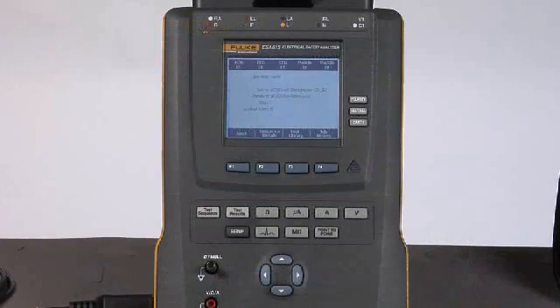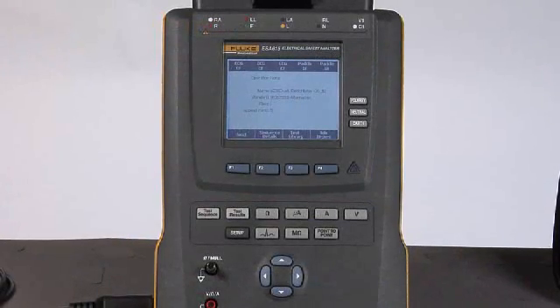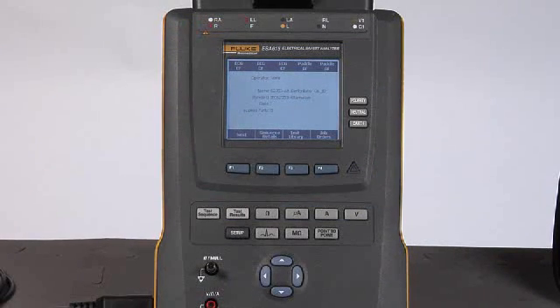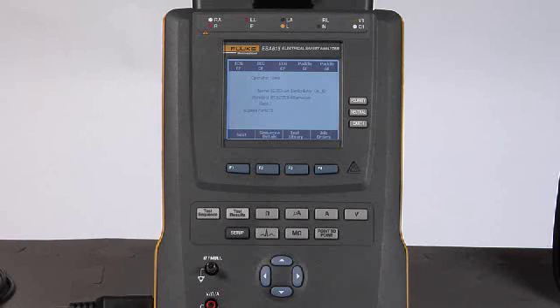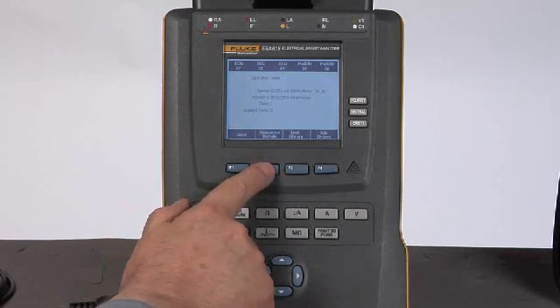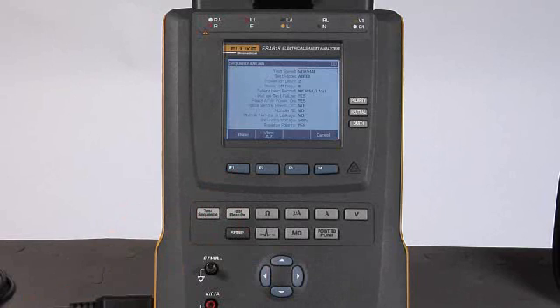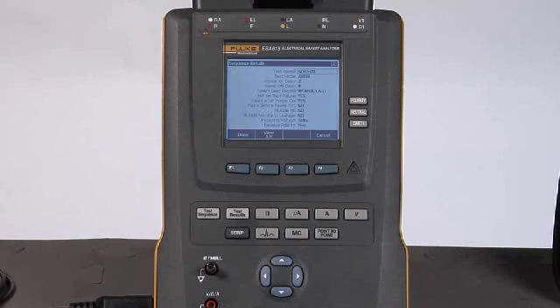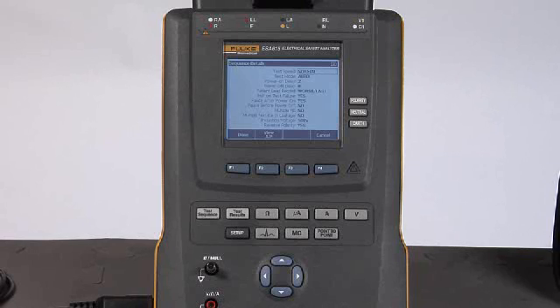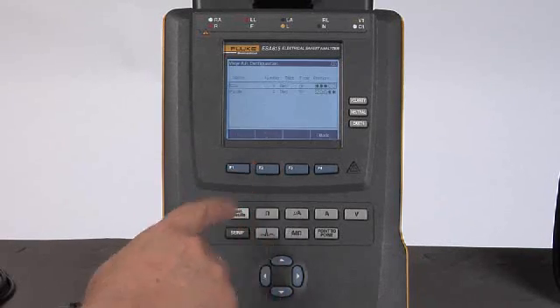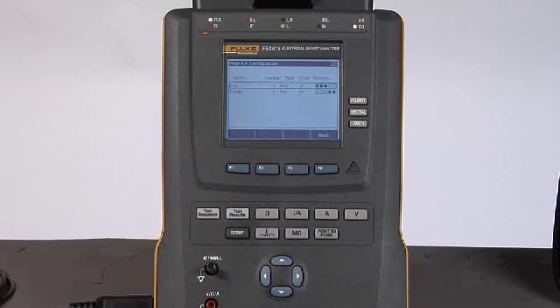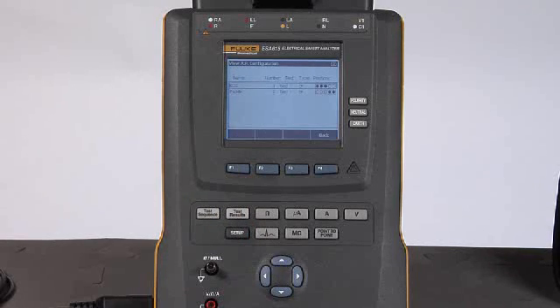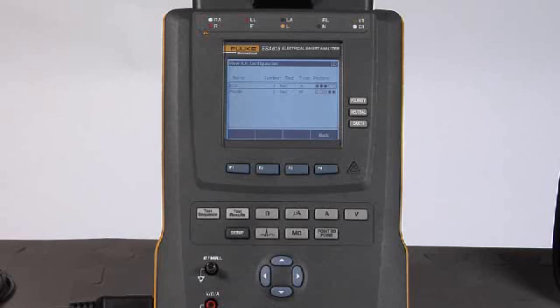If I want to see the details about this test sequence before I run it, just to be sure that all of the control parameters for the test sequence are as I expect them to be, I will press the F2 button. And now I can use the navigation arrows to scroll down through each of the test steps in the test sequence to make sure that they are set properly for what I need to do. The view applied part button allows me to set up my applied part modules—that is, which groups of patient applied connections should be tested together and in what particular way.